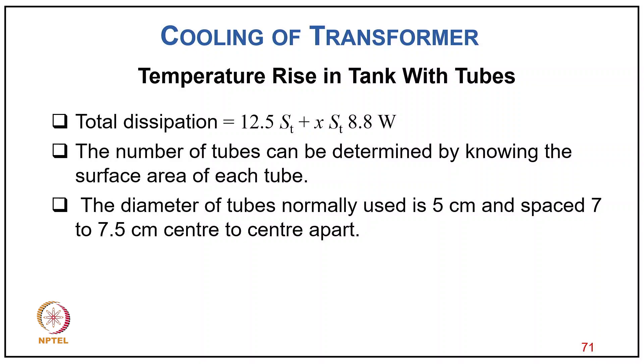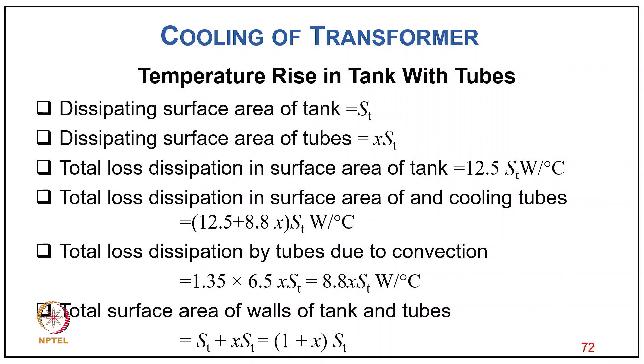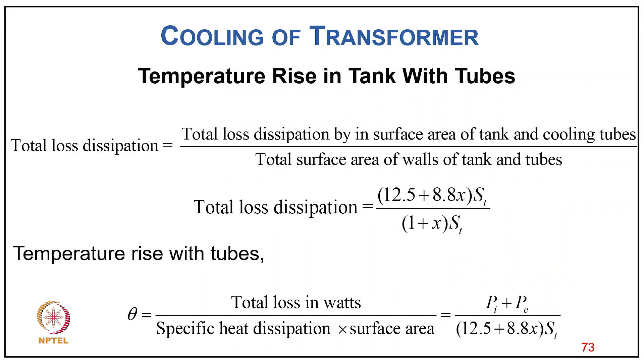The number of tubes is determined from the surface area of each tube, with tube diameter typically 5 cm and center-to-center spacing 7–7.5 cm. Total dissipating area of tank is ST, of tubes is X×ST. Total temperature rise: θ = (Pi + Pc) / [(12.5 + 8.8X) × ST]. Solving for X: 8.8×X×ST = (Pi + Pc)/θ − 12.5×ST, giving X×ST = (1/8.8) × [(Pi + Pc)/θ − 12.5×ST]. Total tube area = X×ST.